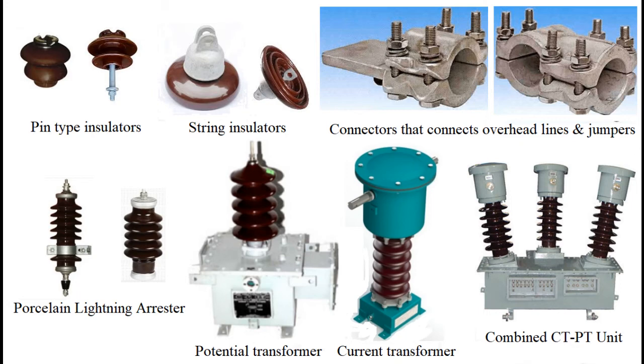Pin-type insulators are vertically placed on top of the C-type channel for each phase. String-type insulators connect two ends of hanging overhead conductors. This arrangement is similar and common for 11 kV, 22 kV or 33 kV conductors. For structural strength of the pole structure and to keep it in vertical position, a tension iron rope is provided at a proper location and direction. This feature is more important in case of a two-pole structure.